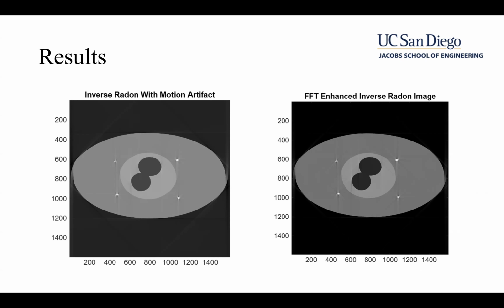Most of the motion artifact correction software that is implemented now, you go to the first reconstructed picture that looks like this, and you highlight those dots that are obviously artifacts, right? And that takes you back to the sinogram and where you need to pay attention to the sinogram and how to fix it. When you do fix it, you will generate artifacts in other places, right? Because the sinogram is sort of a sum of everything, but it does clean up your target, right?